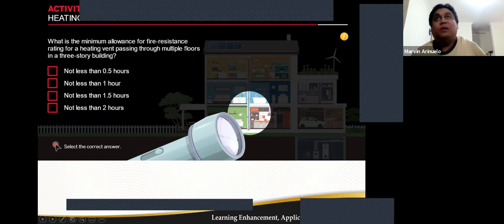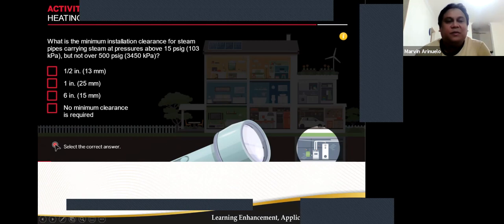Again, according to your fire protection handbook, what is the minimum installation clearance for steam pipes carrying steam at a pressure of 15 psi gauge but not over 500 psi gauge? According to your fire protection handbook, table 10.2.4, the clearance for steam pipes carrying steam pressure over 15 psig but not over 500 psig is 6 inches or 150 mm. So the answer here is C.